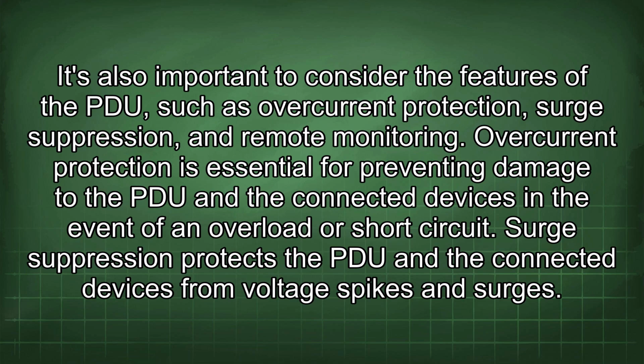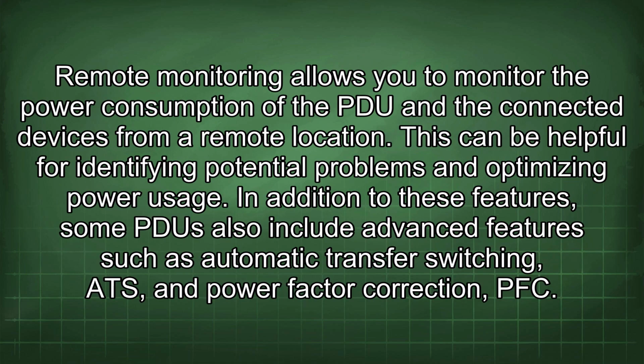It's also important to consider the features of the PDU, such as overcurrent protection, surge suppression, and remote monitoring. Overcurrent protection is essential for preventing damage to the PDU and the connected devices in the event of an overload or short circuit. Surge suppression protects the PDU and the connected devices from voltage spikes and surges. Remote monitoring allows you to monitor the power consumption of the PDU and the connected devices from a remote location. This can be helpful for identifying potential problems and optimizing power usage.